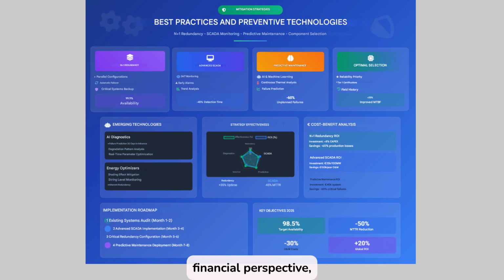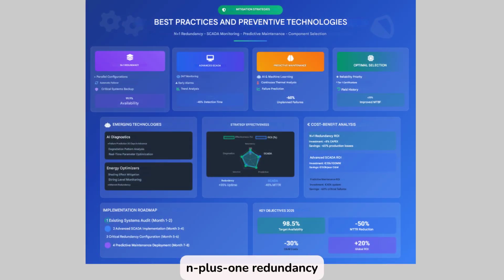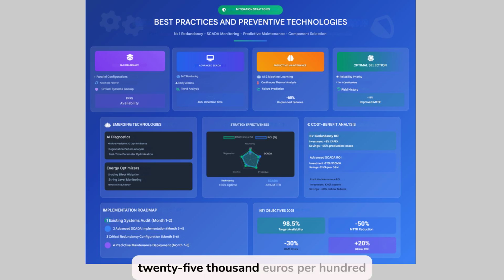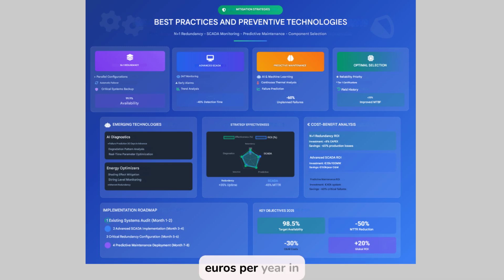From a financial perspective, all of these strategies have a clear return on investment. For example, N+1 redundancy implies an 8% increase in CAPEX, but saves up to 65% in losses due to production downtime. Advanced SCADA, with an estimated cost of around €25,000 per 100 megawatts, can save up to €150,000 per year in O&M costs. And predictive maintenance, with an investment of around €60,000, can reduce critical failures by 60%.